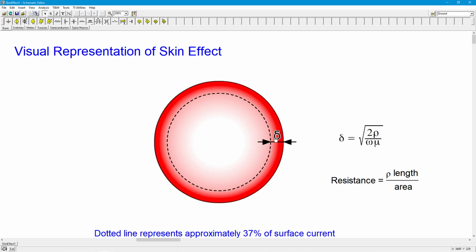too big, right? Even at a low frequency, like 60 hertz, skin depth is somewhere around, I think, about 0.3 of an inch. It's like a centimeter sized. Okay, it's not that much. So it doesn't make a lot of sense, if you have a demand for a high current, to have a conductor that's like 20 centimeters across, like 6 inches across, something like that, because even at 60 hertz the skin depth is going to have an effect. Okay, not at DC, but even at 60 hertz, which we tend to think of as a pretty low frequency, right? That can be a problem.